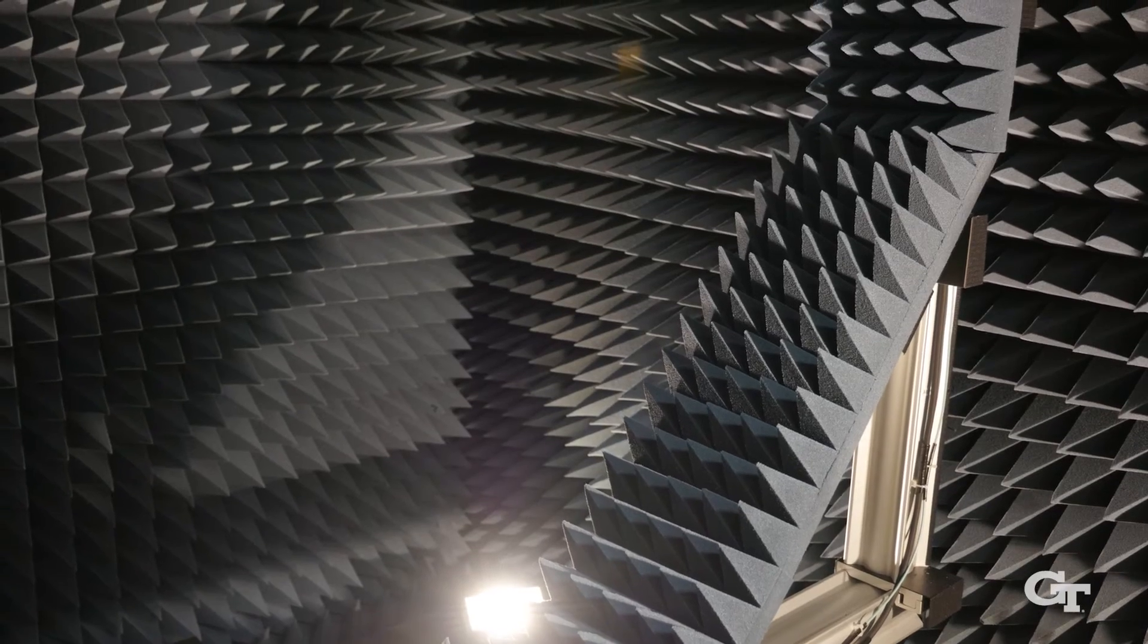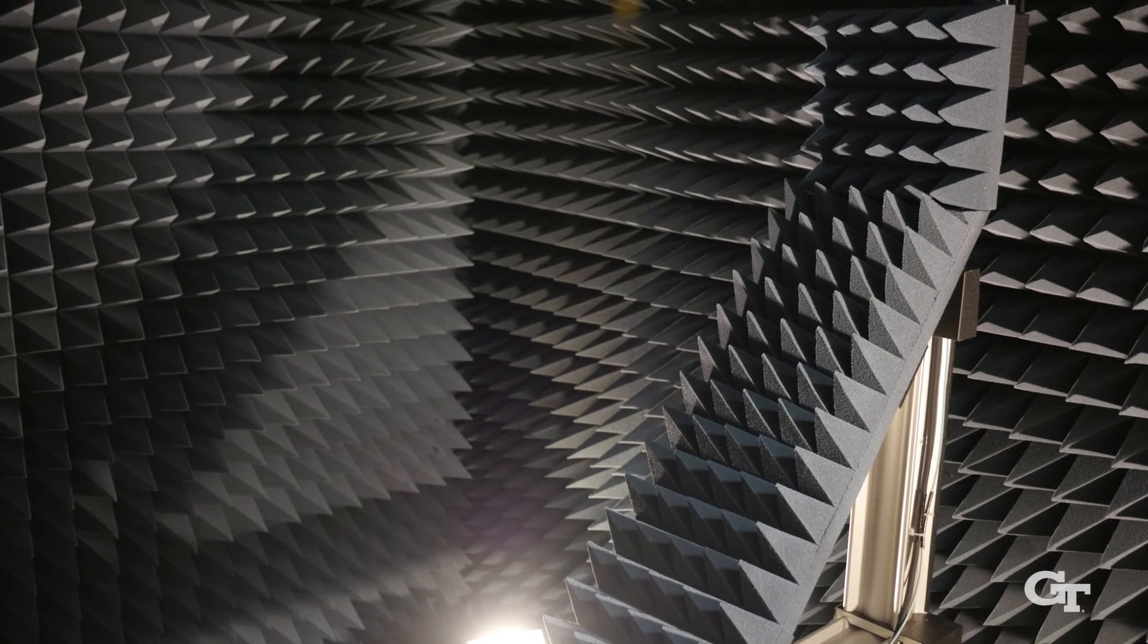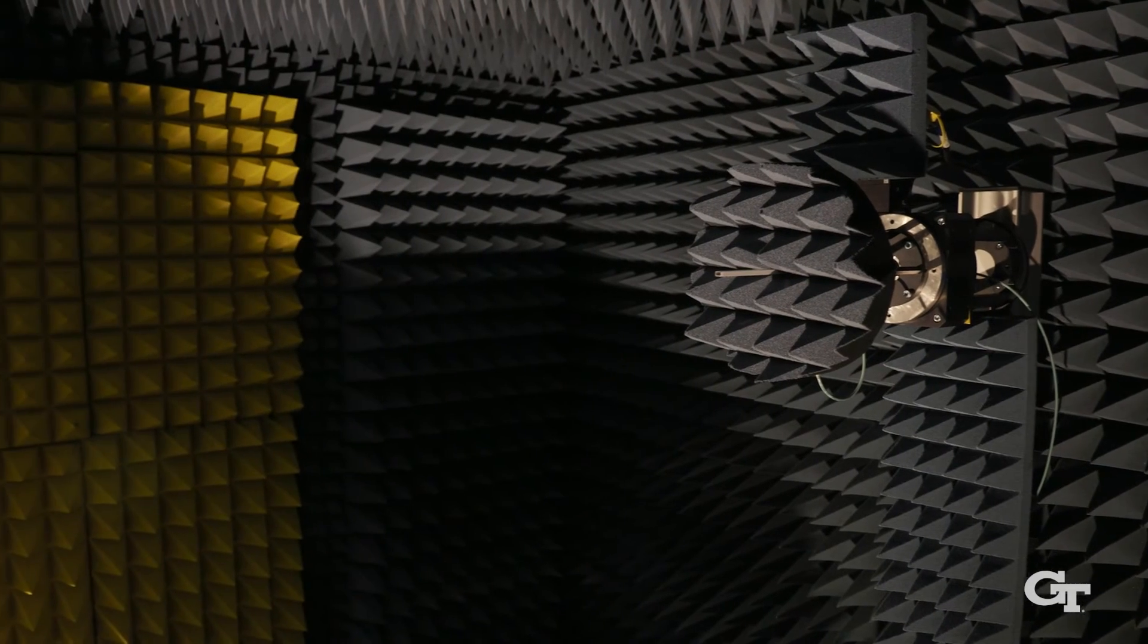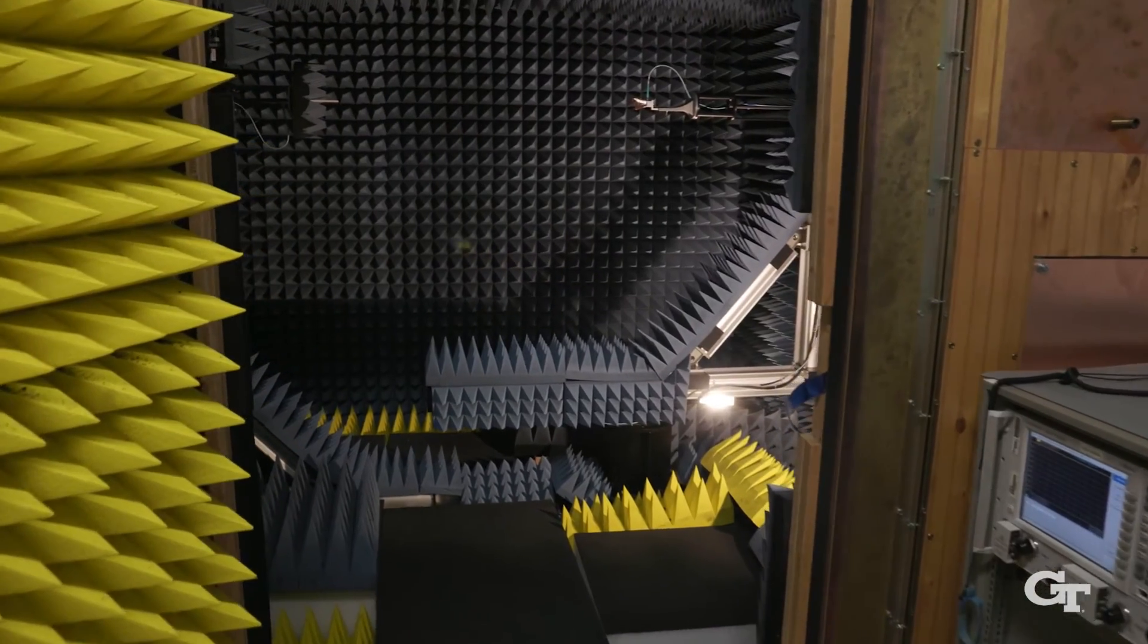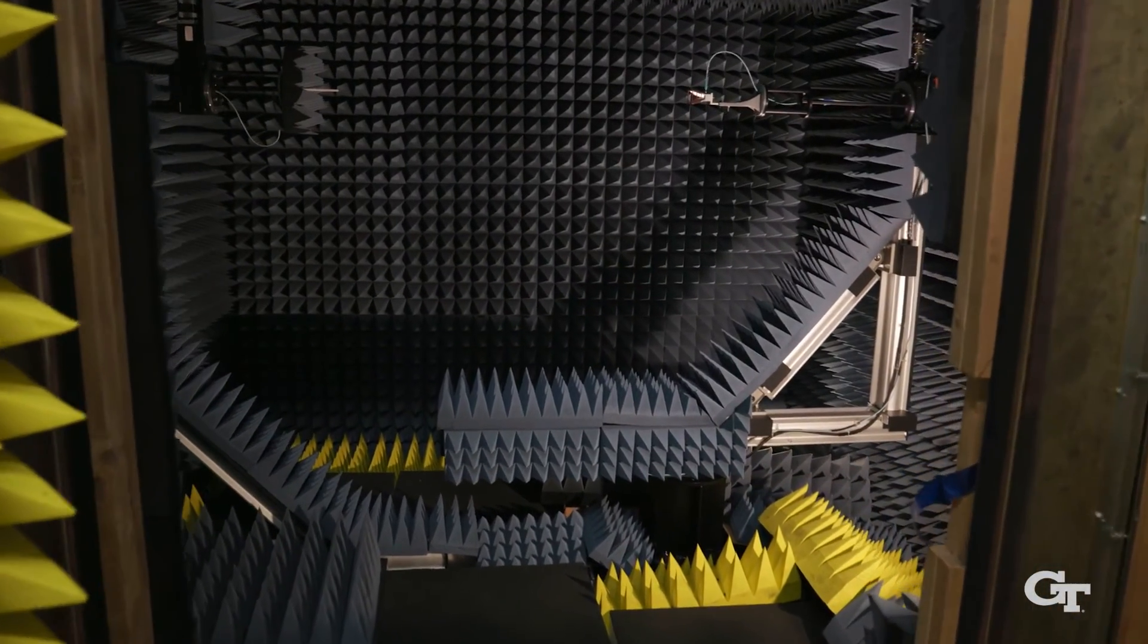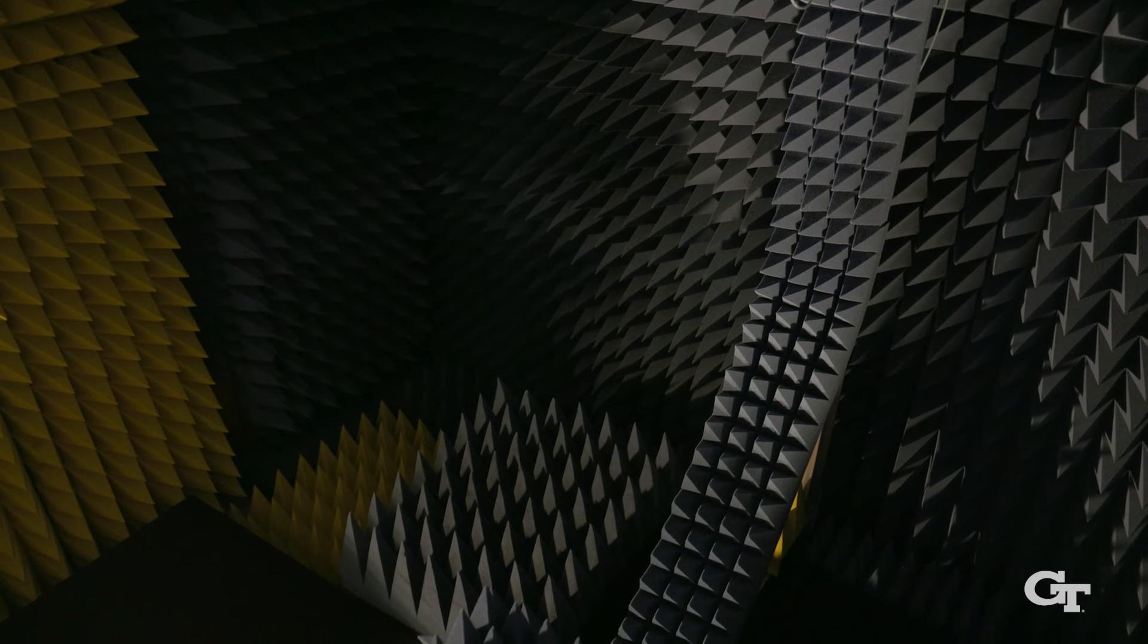Inside the chamber, you can see absorbers that act as a perfect matching layer preventing reflections from the chamber walls. We've also installed walk-free absorbers so that our students can easily walk to the antennas and mount the hardware.